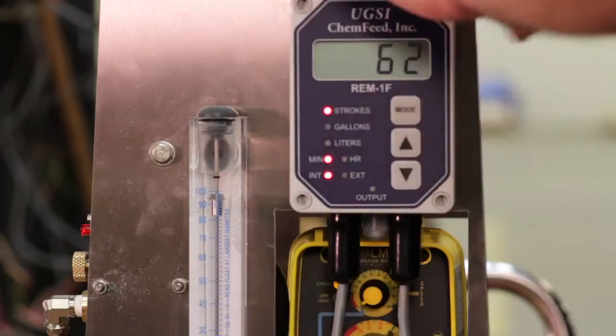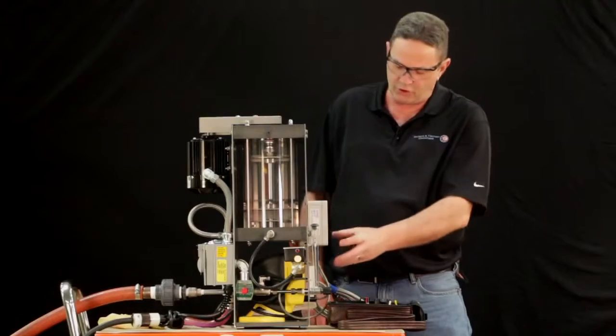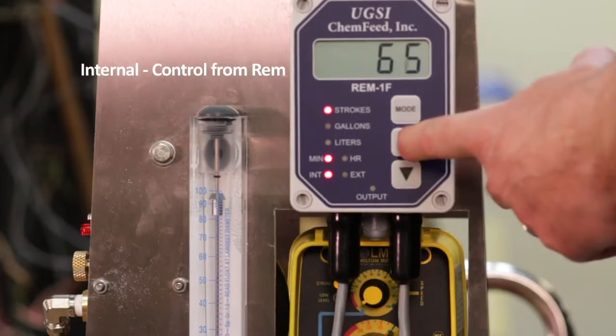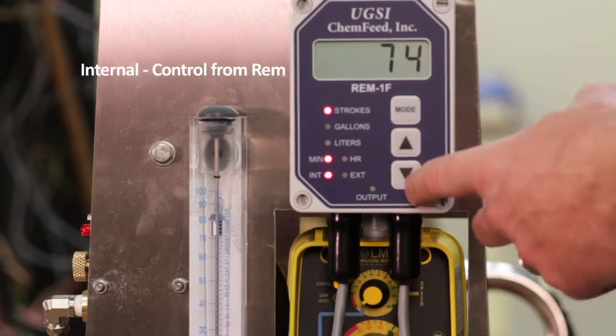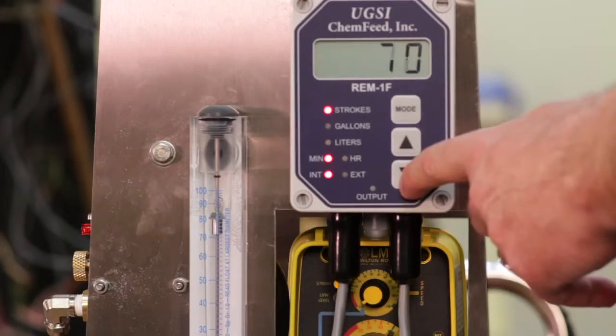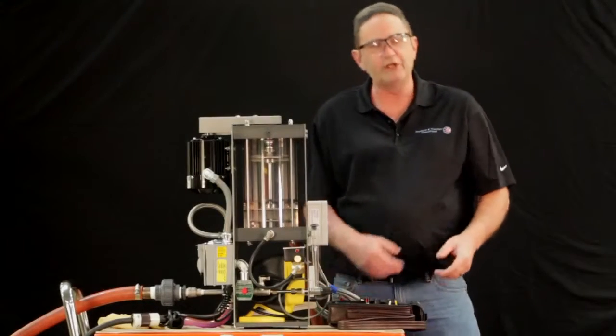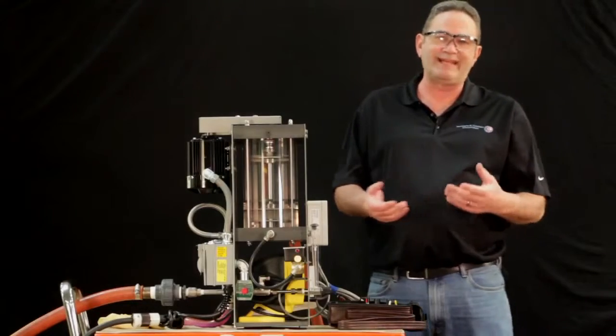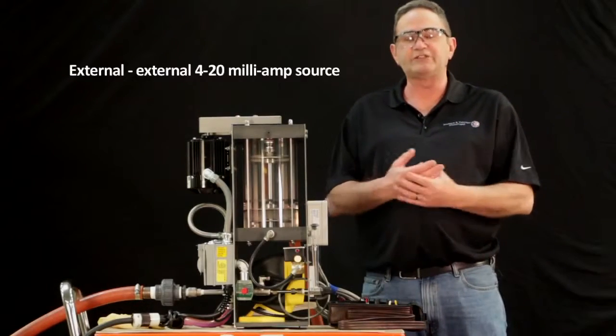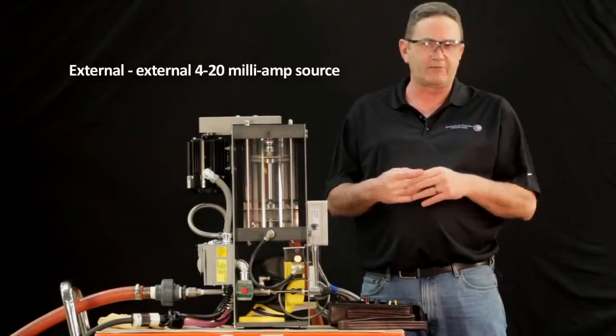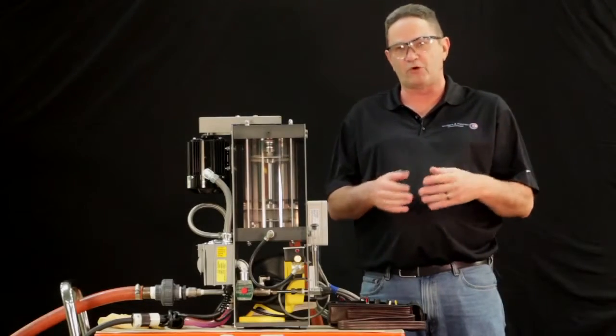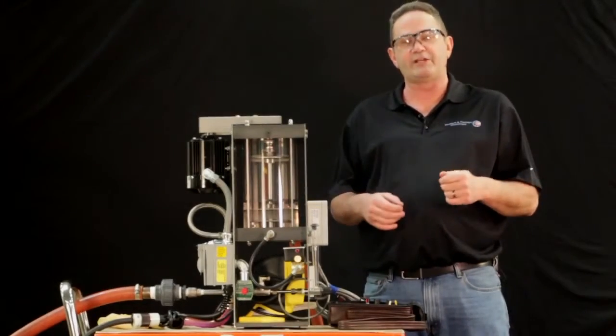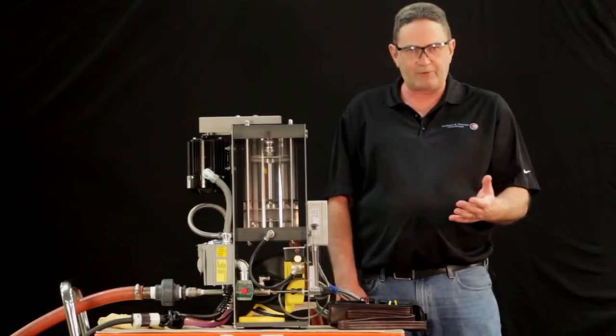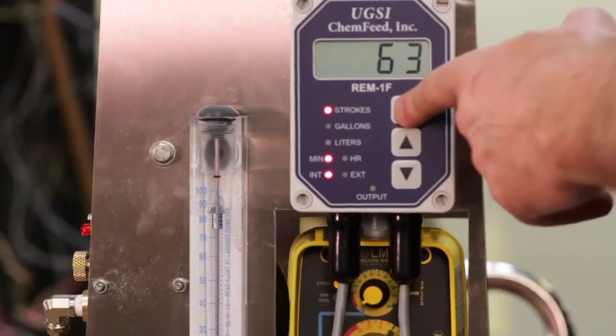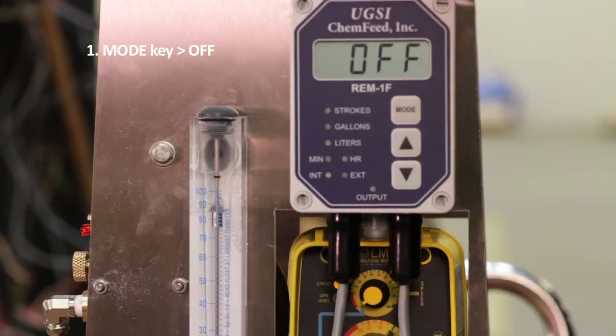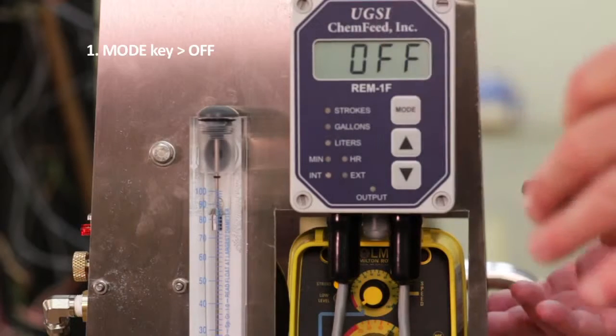Internal meaning, internally, is from the REM controller. You increase your strokes, up or down, or we can use it external. External meaning that you have an external 4 to 20 source. It could be from your SCADA, it could be from your control room, it could be from the point of application. To set this up for external, you simply hit the mode key, it turns your REM off, which de-energizes your polymer pump.